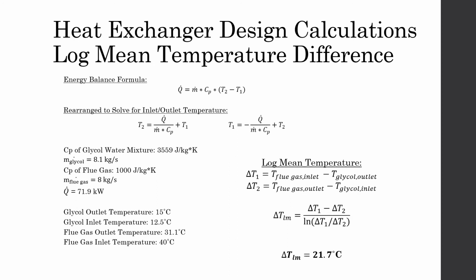The glycol entering the ramp must be 12.5 degrees Celsius at a flow rate of 8 kilograms a second to provide the ramp with enough energy to meet the snow melting requirements. These values were found in earlier calculations. Analysis of the heat exchanger used an outlet temperature of 15 degrees to add a factor of safety. While no data exists for the amount of flue gas exiting the university stack, a comparable stack found within the Guelph region was found to have an exhaust mass flow rate of 8 kilograms a second.